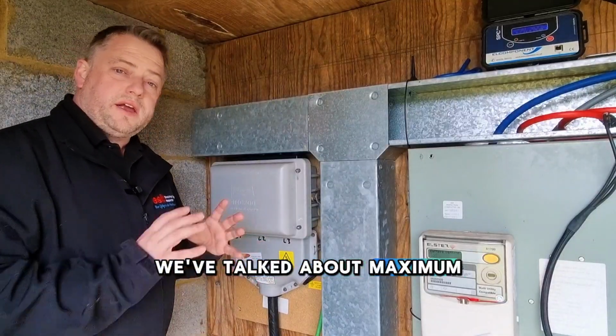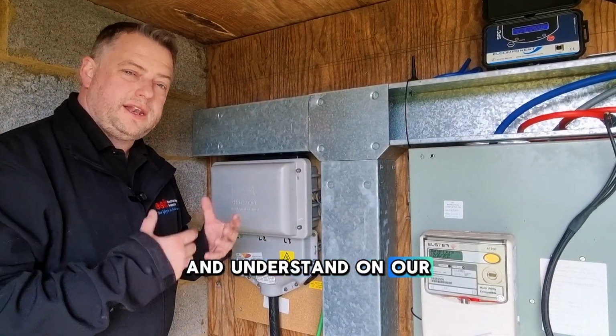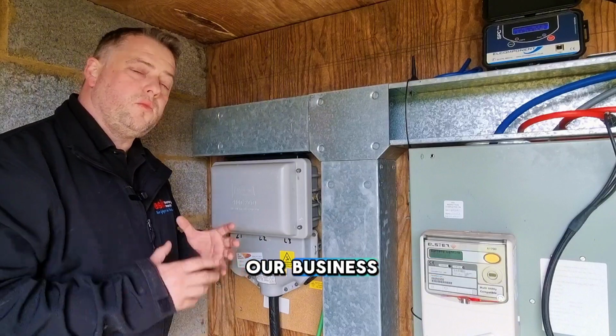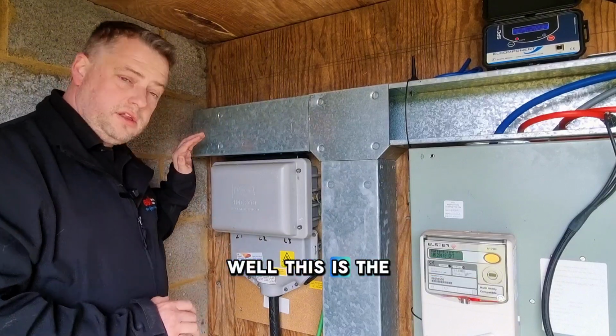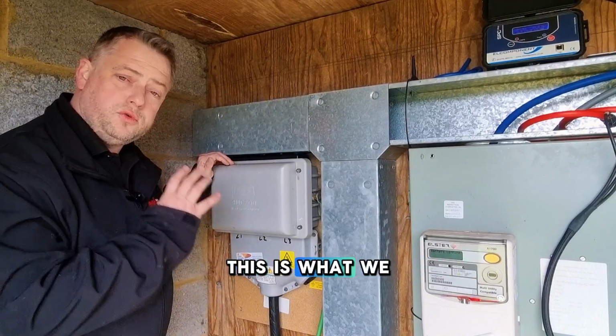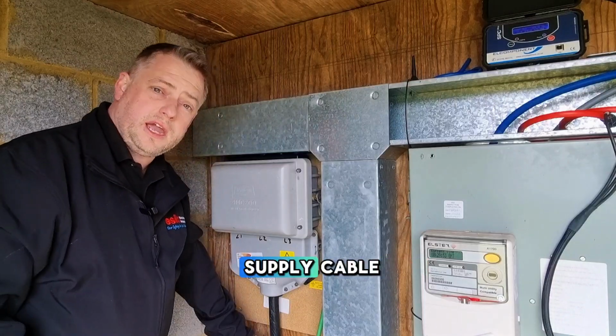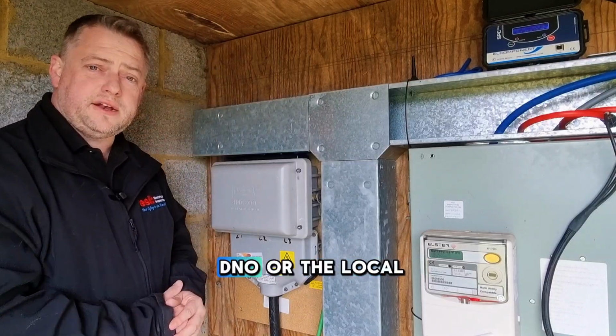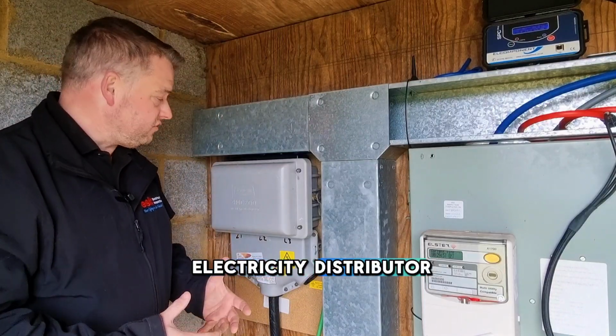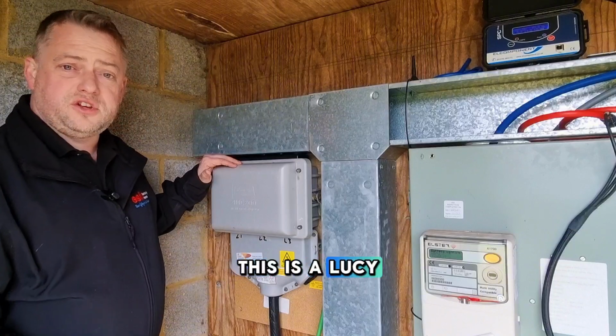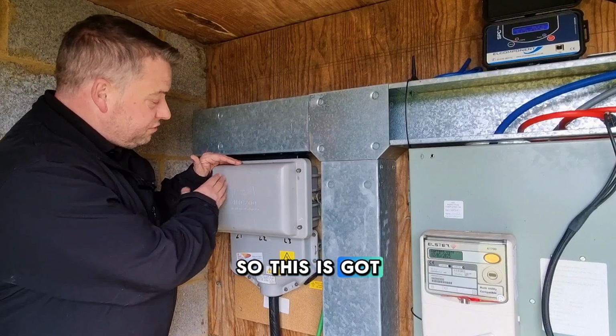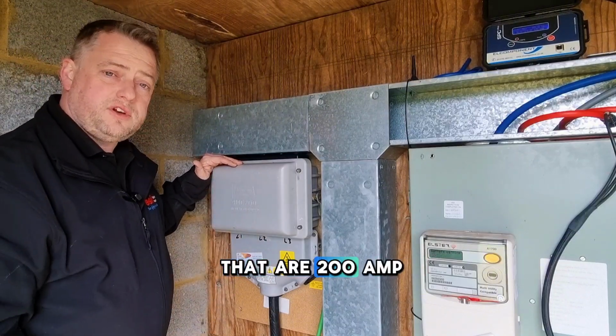We've talked about maximum demand and understanding our electrical load profile within our business, but why is it really important? Well, this is the incoming electrical supply. This is what we call the service head, and this is the supply cable or service cable. They come from the DNO, or the local electricity distributor. This is a Lucy 200 amp service head, with 3 fuses in here rated at 200 amps.